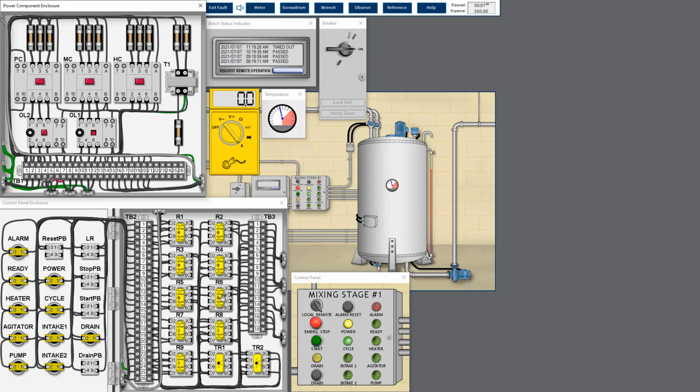There's a few types of current. Full load current is a normal current. When the motor is running, it must run on the full load current. It's a must. Another one is the no load current. That means maybe the pump and motor are disengaged, so there's no load. So with the motor running on no load, the current will drop, so it's a no load current. The other one, overload current. When there is an overload, whether electrical overload or mechanical overload or process overload, you will get the overload current, which is higher, maybe 7 times higher than the full load current.